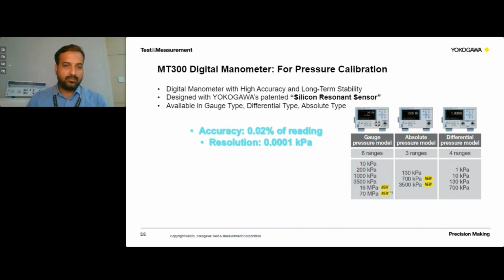So one of the importance of these manometers is with respect to accuracy and resolution. As you can see here, these manometers have 0.02% of the reading. In the previous slide, we discussed what is full scale error, what is percentage of reading error, and how it is going to define the accuracy or the capability of the particular master instrument. So from that perspective, these manometers have got 0.02% of the reading accuracy, which is highest available in these ranges, and resolution of 0.0001 kPa. Resolution means we will be able to measure the pressure deviation up to the 4th decimal point.